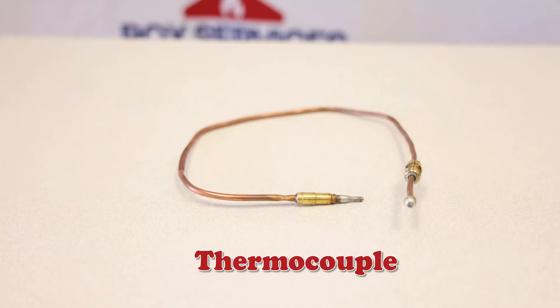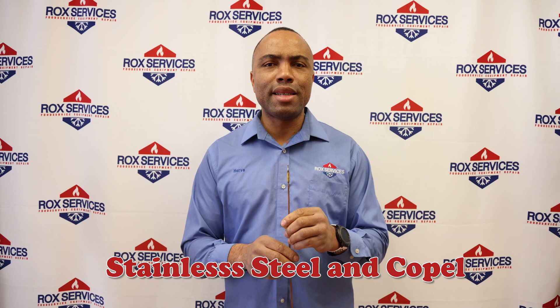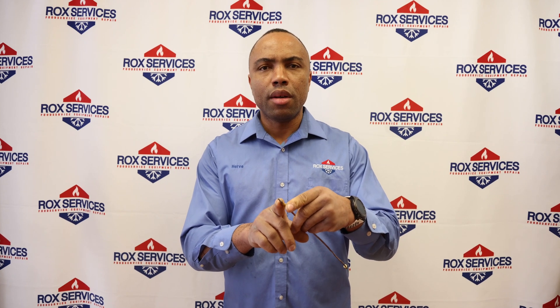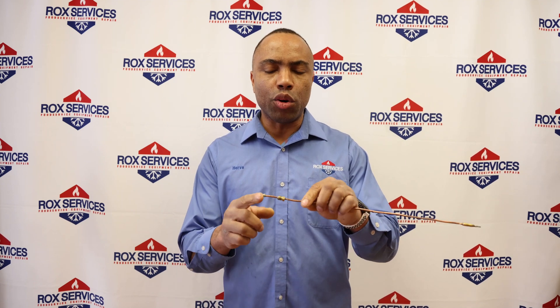A thermocouple is a small device that we use in food service equipment to power the safety gas valve. It's made from two welded metals — one is stainless steel and the other is Copel. By welding those two metals at the tip, if you heat that tip you are going to generate millivolt DC at the other end.